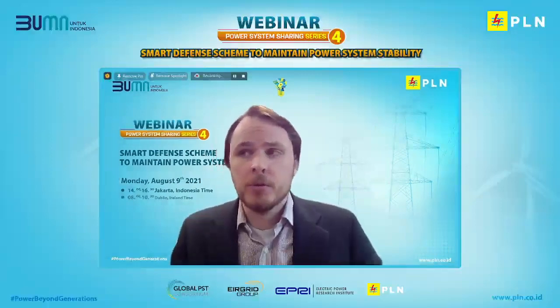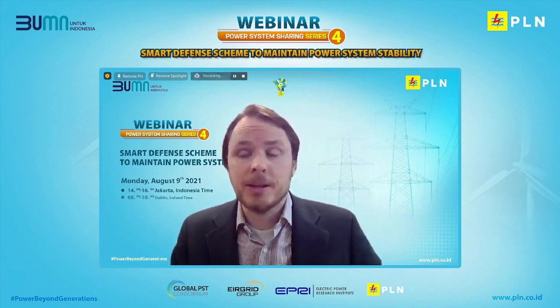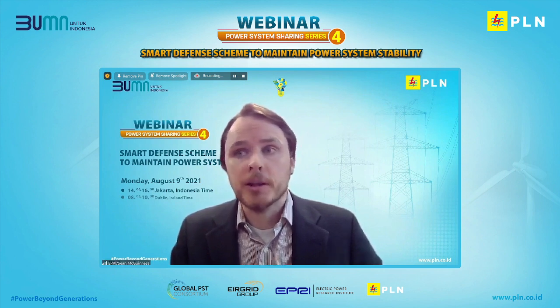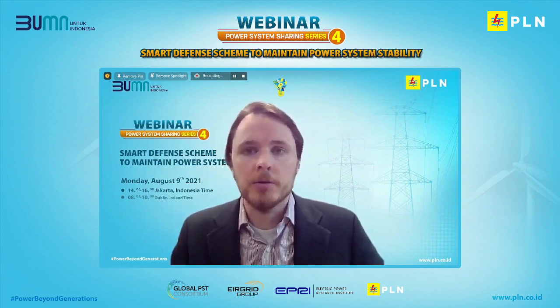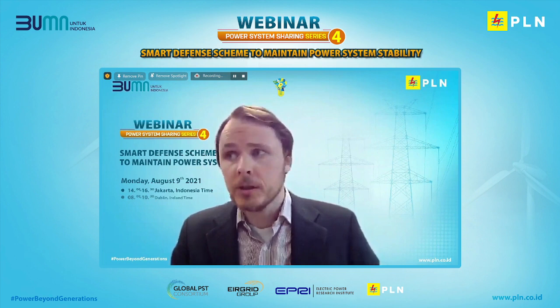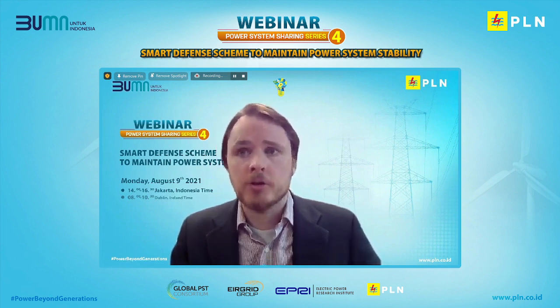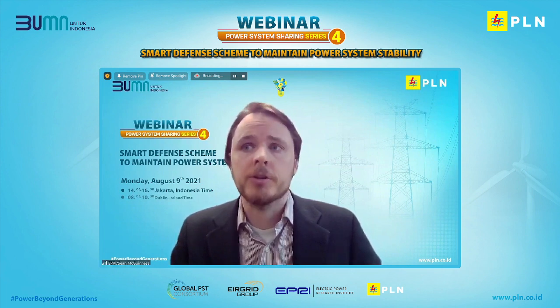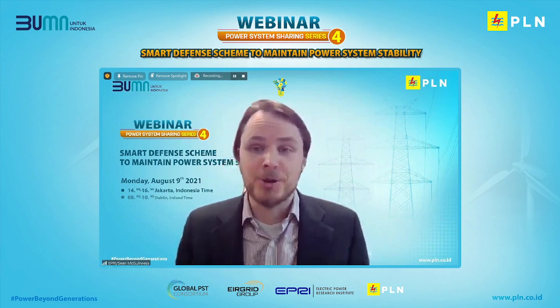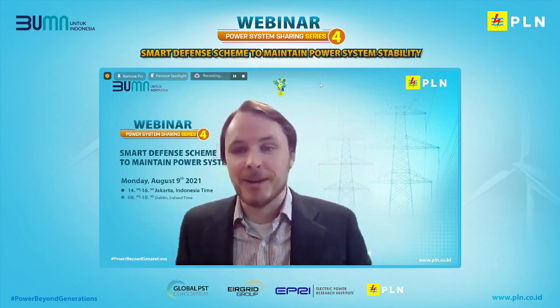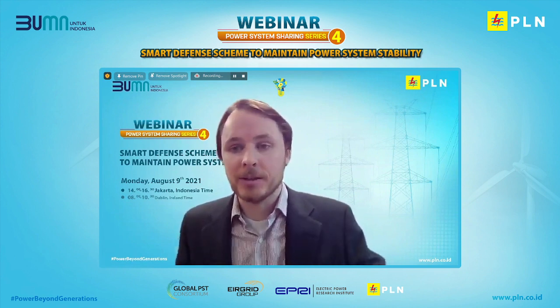And unfortunately, for those types of events, it's very hard to predict what can go wrong. And I'm not aware of any scheme or design that allows total flexibility and resilient response. But I guess the big thing is that you know your grid, you understand your grid, and to try and study as many credible scenarios at the planning stage is the best way to design a resilient system. That's pretty much all you can do, and ensure that the communications and the relays are reliable and redundant to prevent failure. So unfortunately, there's no magic answer to that, apart from doing your homework and doing as many studies as possible at the planning stage.